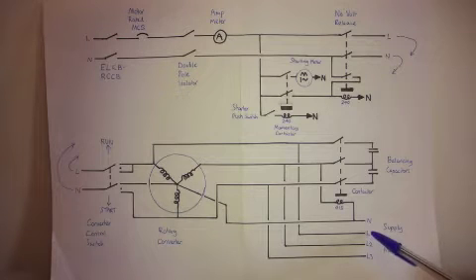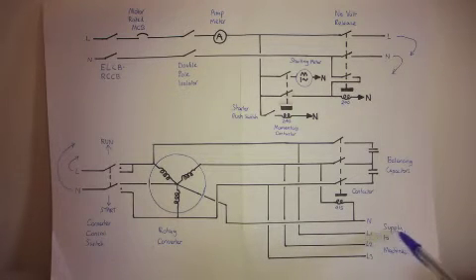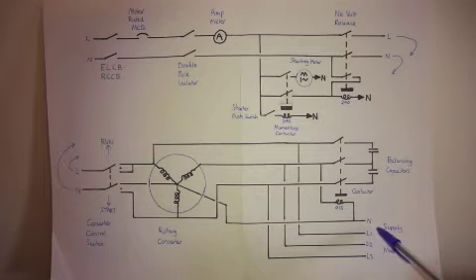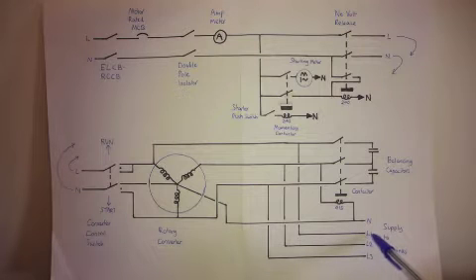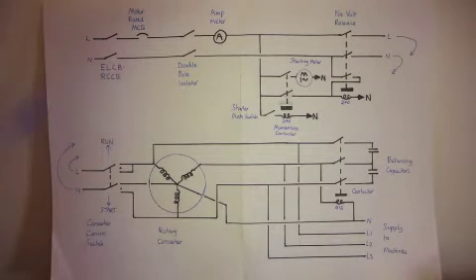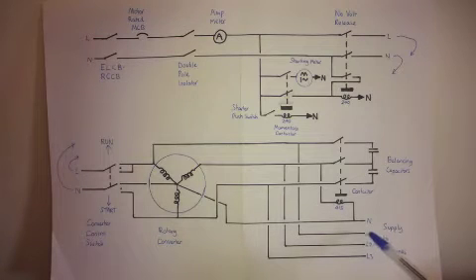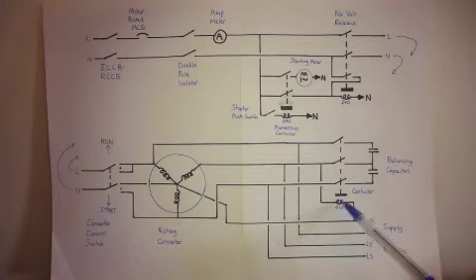Down here is the supply to the machines. The only thing I'd say about that is that in wiring my machines, each of them will have a no volt release starter, direct online starter, and in wiring my machines, I've always ensured that the strongest phase, L1, which is the true live back here, forms one side of the coil upon which the contactors operate.